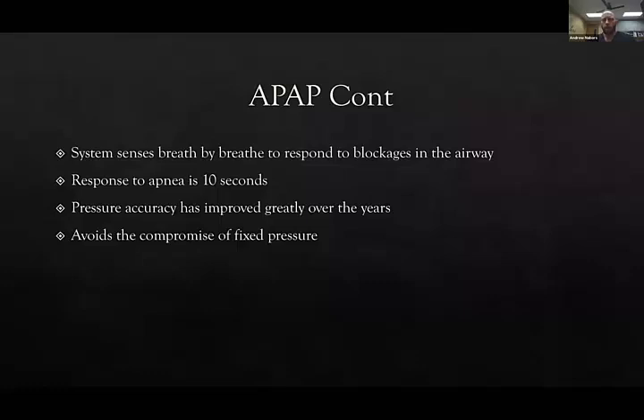You know, the other thing about an APAP machine is it does adjust pressures. And of course, it's adjusting pressures based on the demands of the person. Now, a general definition of an apnea is a 10-second breathing pause. And these machines have to wait at least 10 seconds for a response. Otherwise, it could get aggressive if you took a yawn or just had a longer breath, and then the system started to go aggressively at you.